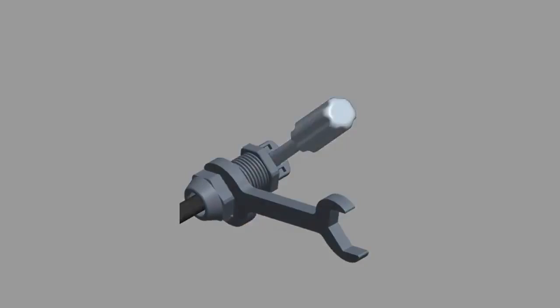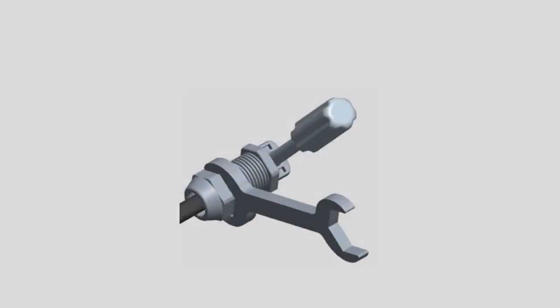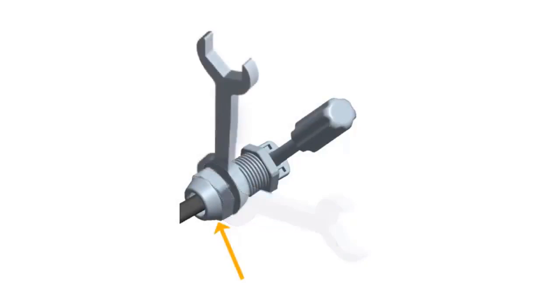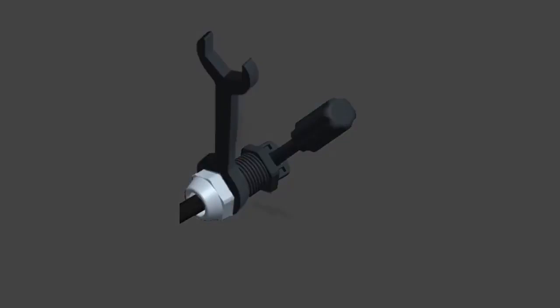Hold the terminator body stationary with a screwdriver and turn only the hex nut to prevent the conductors from twisting out of the separator. Be sure to only tighten the hex nut. Rotating the terminator body could cause the conductors to back out past the internal separator. Warning: never unscrew the hex nut. Unscrewing the hex nut destroys the locking feature and you must replace the terminator.